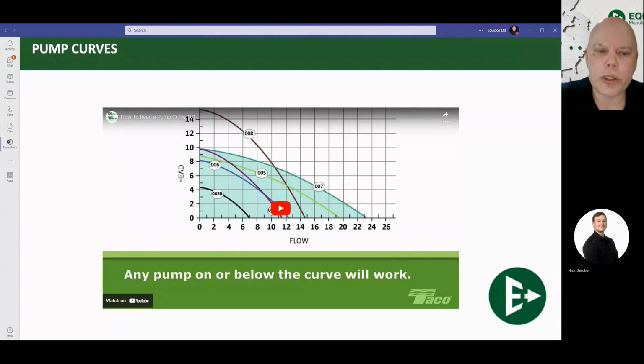Now this video is going to show you how to read and work with a pump curve. We talked about how you can figure out the GPM required. I want you to keep that one in mind for GPMs for now. The other thing that's going to start to come up in our conversations is what's known as head, or friction, or head loss. That's going to be the second part to this detail as to how exactly these pumps operate and how they work. So without further ado, we're going to watch the video, and then I'm going to take a bit of a deeper dive into head loss and exactly how that works inside of a hydronic system.